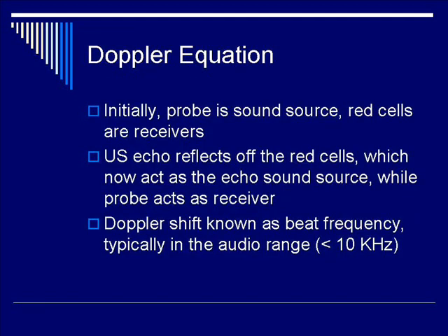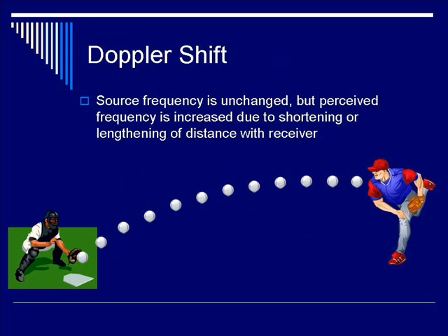In the clinical setting, the probe provides the source of the sound waves and the red blood cells are the receivers. The ultrasound echo reflects off the red cells, which now act as the echo sound source, while the probe becomes the receiver. A Doppler shift is detected from the difference in frequency between the transmitted pulse and the received pulse. It's important to remember that the source frequency is typically unchanged, but the perceived or received frequency is either increased or decreased due to the shortening or lengthening of the distance to the receiver.